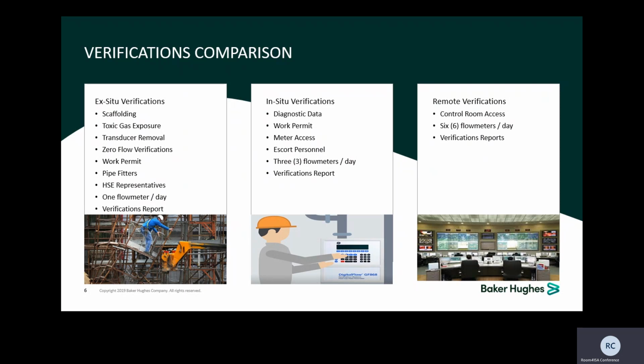So what we did, years later, is come up with the in-situ verification. The in-situ verification eliminates a lot of that laundry list you see with the ex-situ process. Our guys go directly to the meter itself and run diagnostic tests, without having to access the transducers.